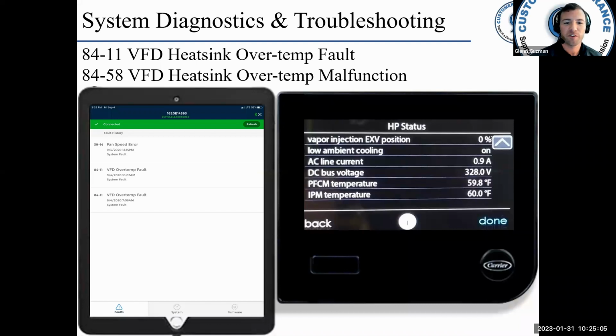8411 and 8458, that's a VFD heat sink over temp fault and heat sink over temp malfunction. So I told you before, there are some internal temperature sensors to monitor critical power components of the VFD. All right.